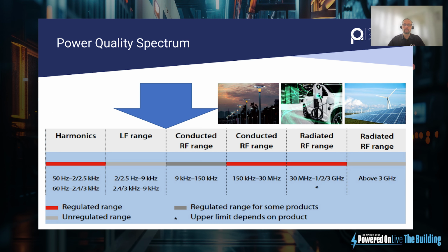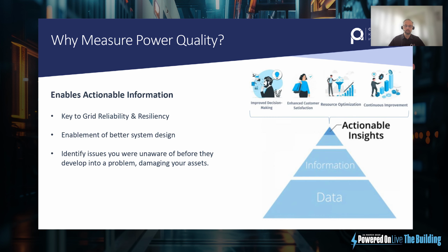So we're not talking about EMC today, that's outside the area we're talking about. But mainly, why am I focusing on this? Because the technology we're talking about today, the EV chargers, are creating noise between harmonics and superharmonics, depending on the level of technology that's being deployed. And depending on the number of these that are being deployed is a factor. And also, are they being interfered with by the production facility, for example? I have a case where I visited a production facility and their equipment was affecting the charger's ability to remain on comms, which we'll talk about later on.